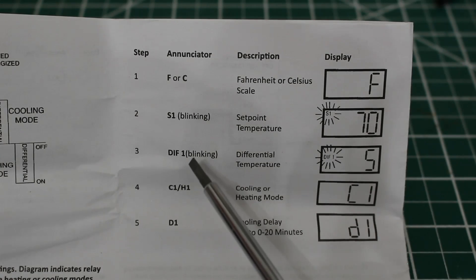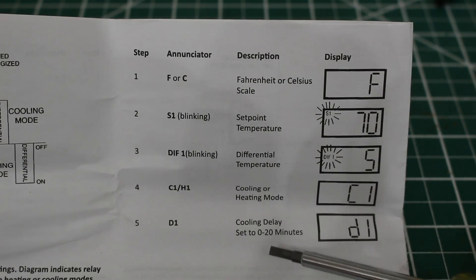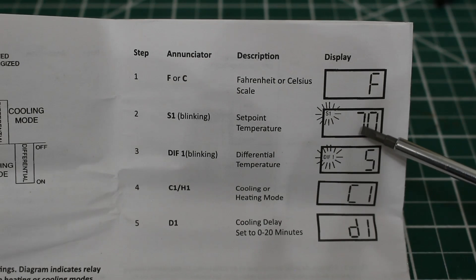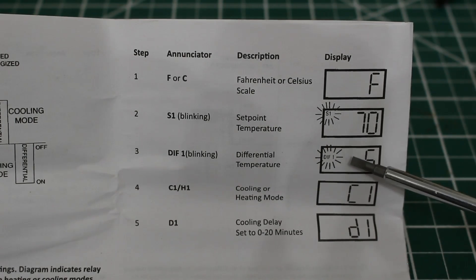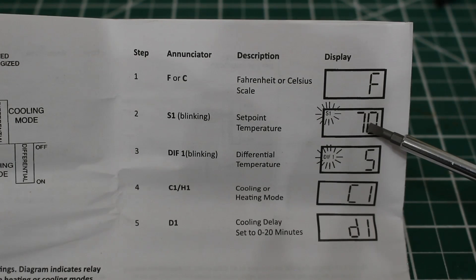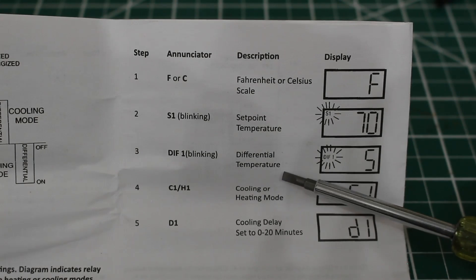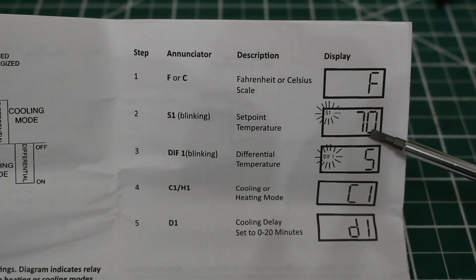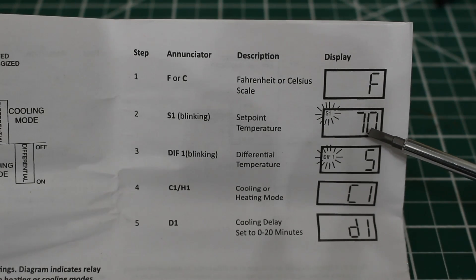Step three — you're going to see DIF1 or just a number, and it's going to be blinking. This is your differential temperature. So let's say you had your set point S1 at 37 and your differential set at 3. That means once the box reaches 40, it's going to kick back on until it reaches 37 and then kick off. So we're going to range between 37 and 40 degrees — that's going to be our on and off set points.